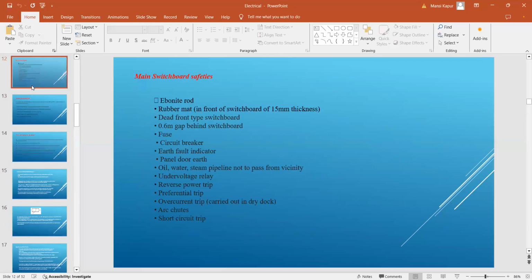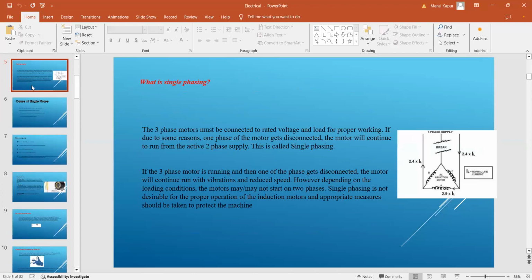So what is single phasing? In a three-phase connection, if one phase gets distorted or disconnected, that is known as single phasing, as you can see in the diagram also. Can you see this phase is getting broken? So this is known as single phasing. Can you look at this diagram and tell me in what connection this motor is connected? Is it star connected or delta connected? Delta connected. Very good. The three-phase motor must be connected to the rated voltage for proper working. If due to some reason one phase of the motor gets disconnected, can you see here, the motor phase got disconnected.